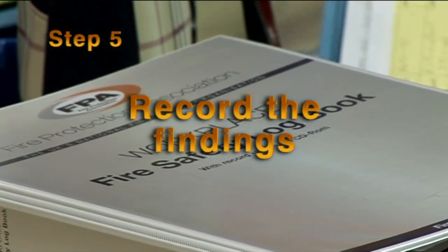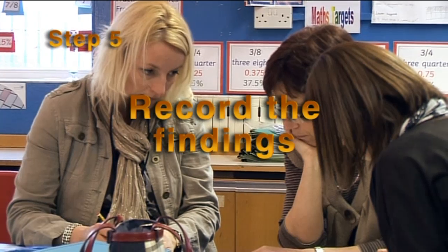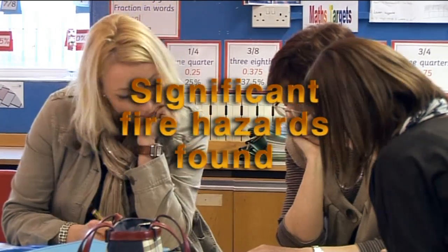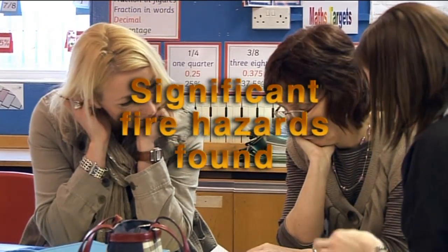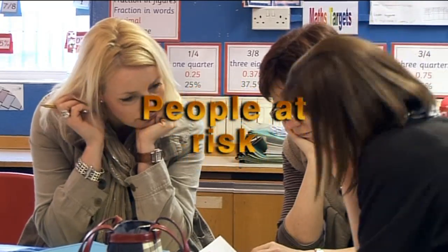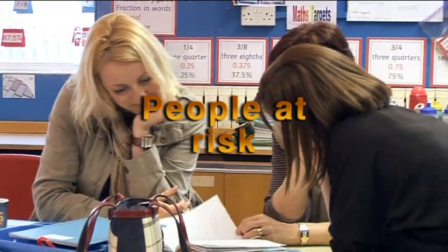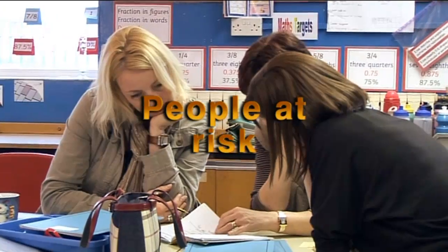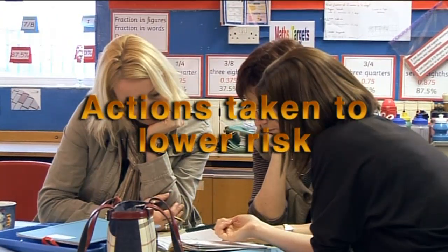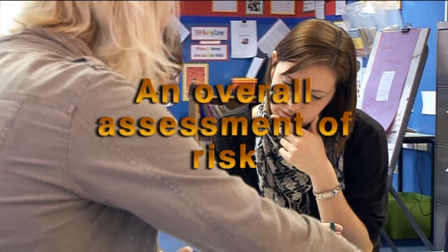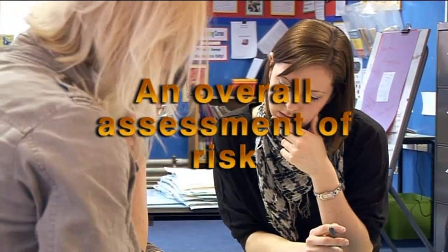All findings from the risk assessment must be recorded and should include any significant fire hazards found, details of any staff, pupils or others who are especially at risk, actions taken to lower the risk, and an overall assessment of the risk.